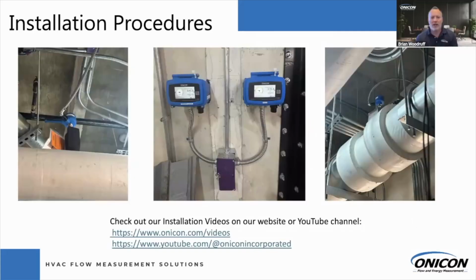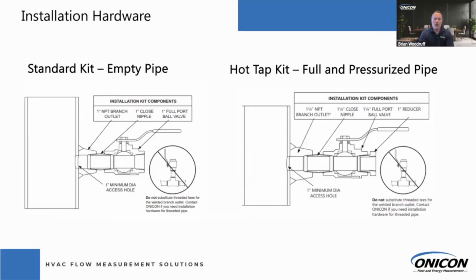All right, so we're just going to touch on the installation procedures real quick on this flow meter. I'd like to refer you to visiting our website and or our YouTube channel, and you'll see all of the installation procedures to hopefully achieve a smooth installation. So also when you order your flow meter, just go ahead and order the kits through ONICON. We have the standard kit available for dry tap, and then we have a hot tap kit available as well. And why that's important is because of the insertion depth that we discussed for the insertion flow meter, you've got to get at that right area in the pipe for the best measurement.